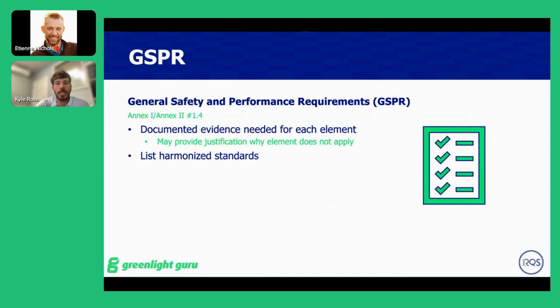The GSPR, I just want to touch on these a little bit. You need to look at this section of the annex and go through each section of the GSPR and document evidence needed for each element or provide justification why it does not apply. So this will reference sections of your procedures, sections of your design control, sections of your risk management, and sections of your V&V within your actual GSPR record.